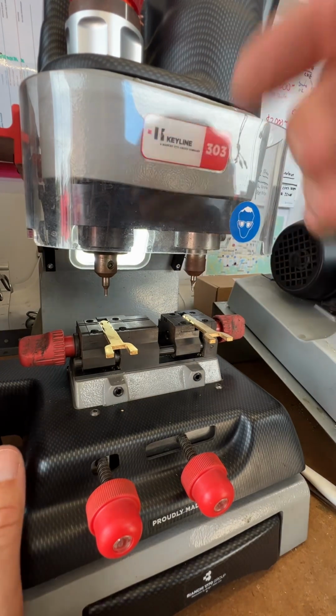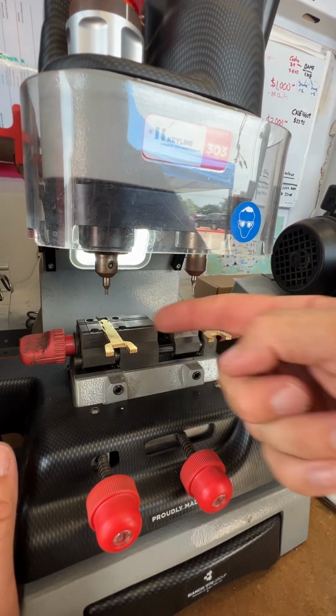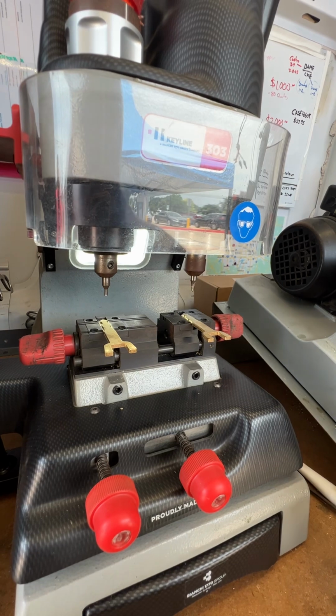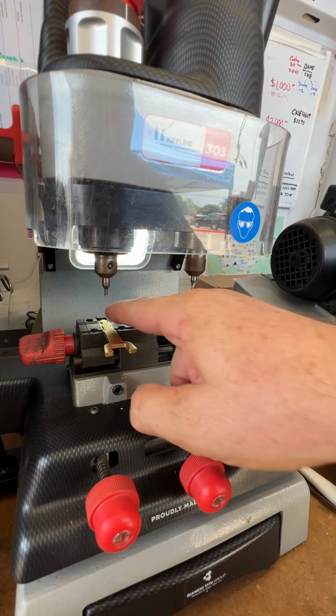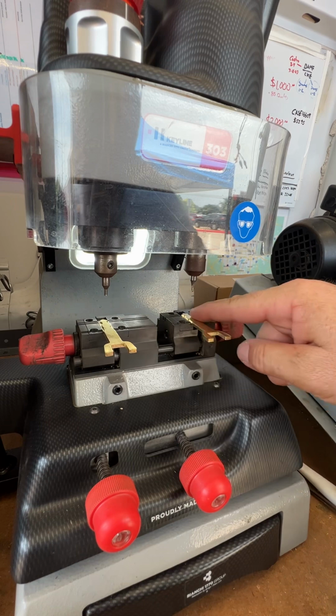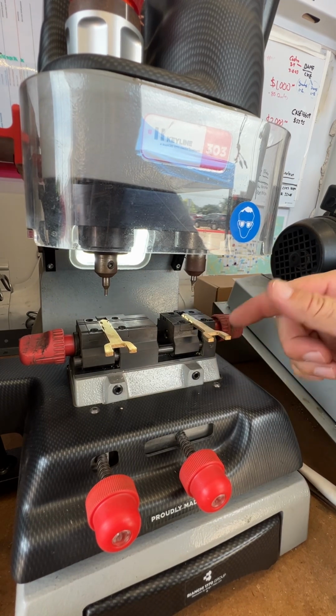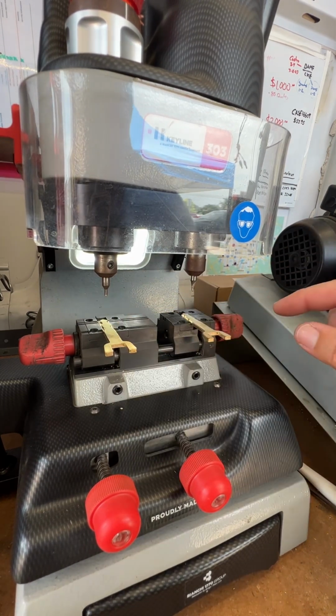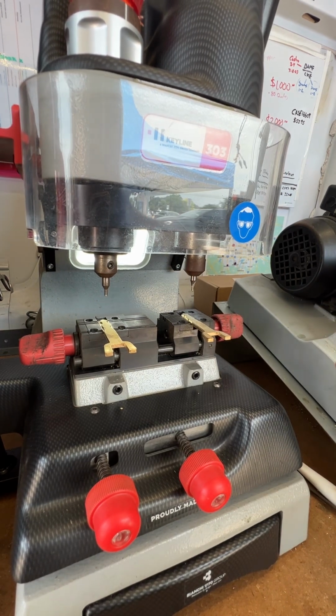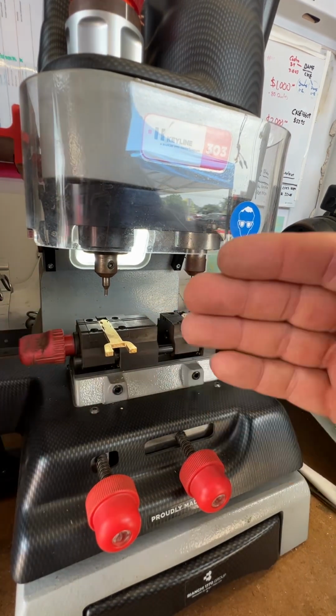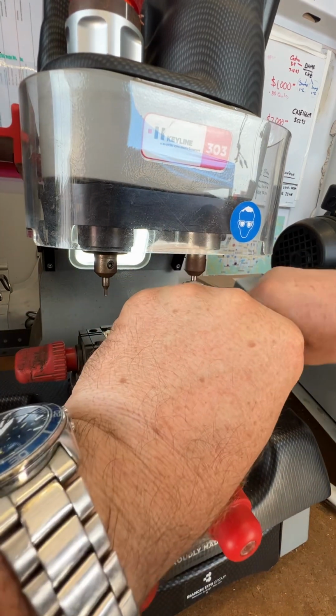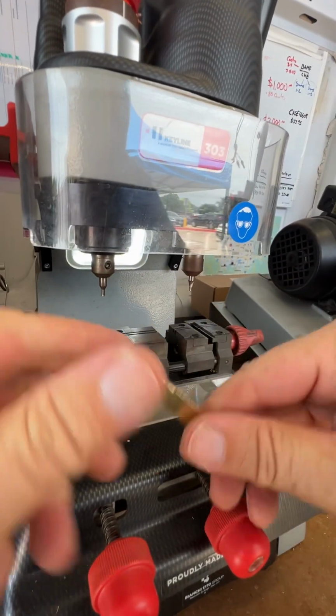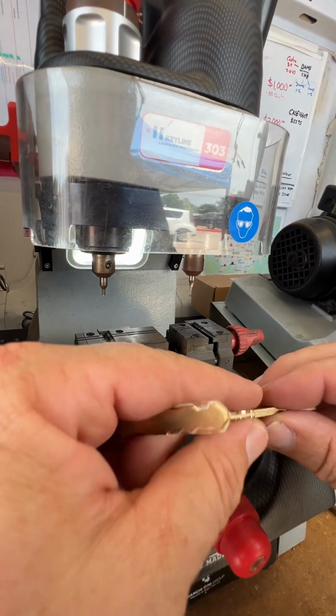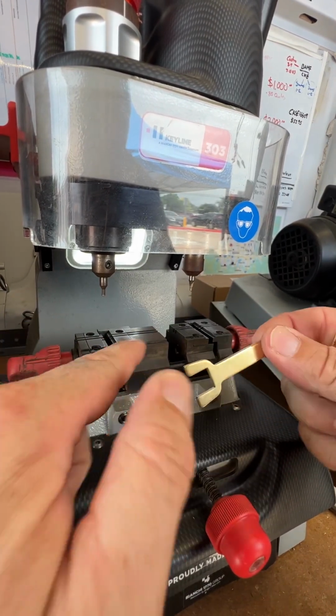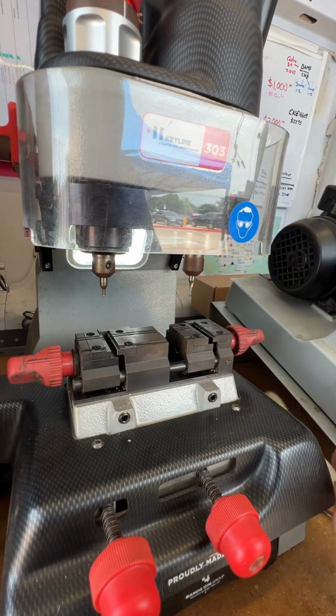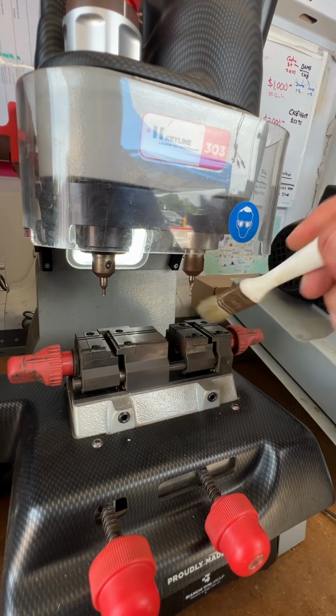So since I'm getting here, here, and here, all three different variations, I'm able to figure out that there's either some sort of debris on here, or I have calibrated wrong, or the key itself is dented or damaged. So instead of trying to figure this out with the calibration, I'm just going to remove the key and check. Are there any burrs, anything like that that would mess up with the plate there? Not sure, I don't see anything. Going to clean, just clean again.